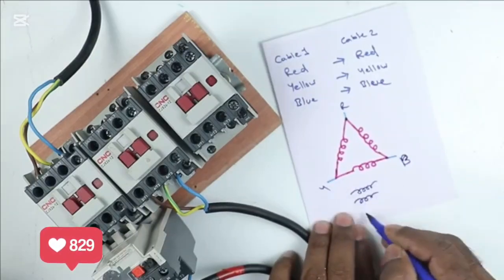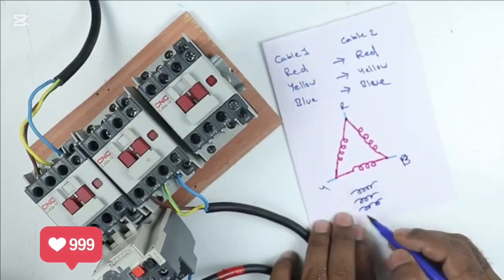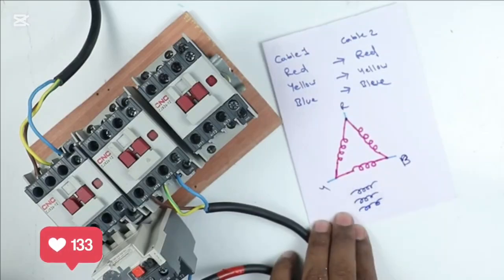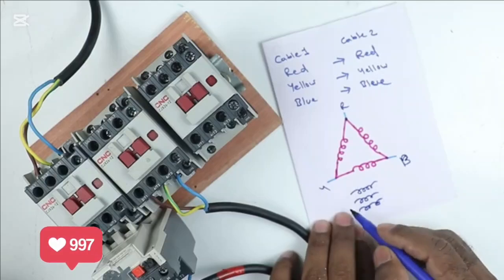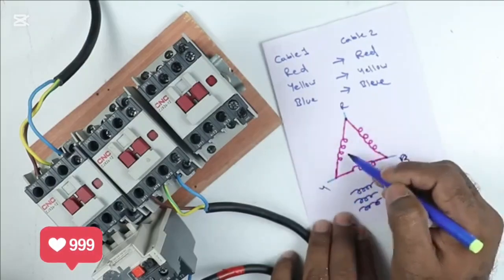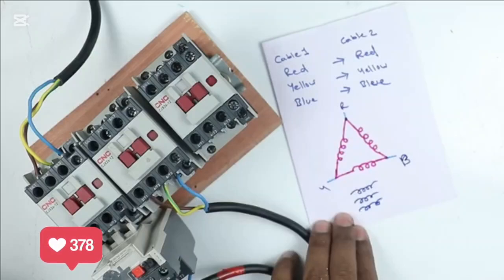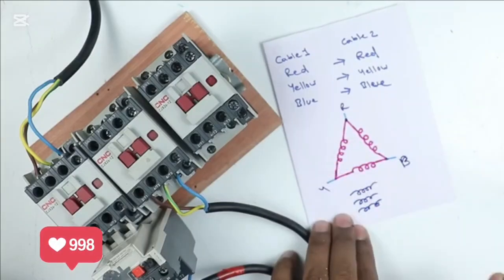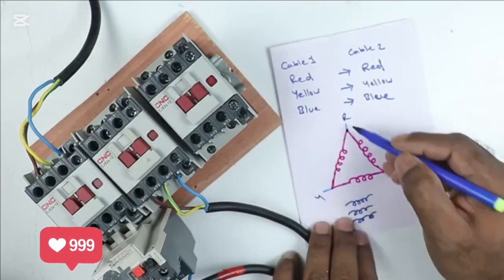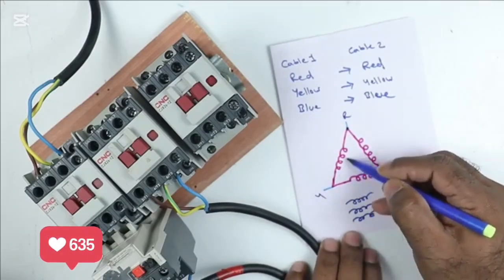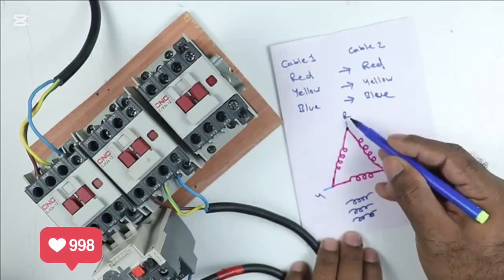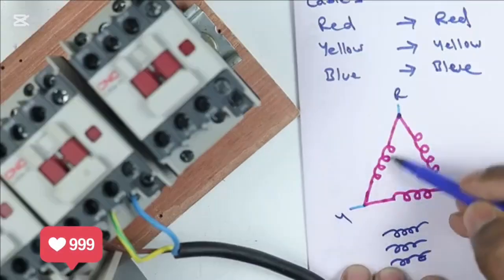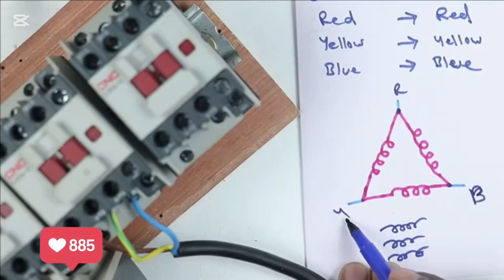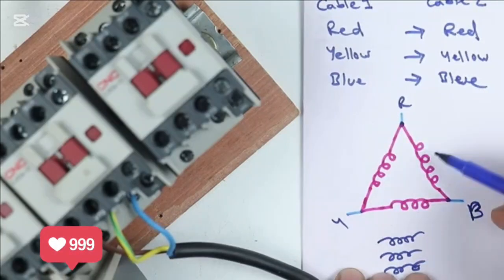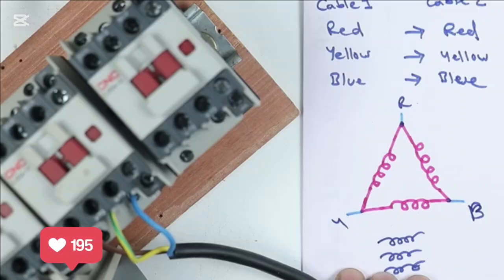Right now the wires which are coming from the motor are in open condition. I mean we have 3 windings and all the 3 windings have 6 different wires. All the 6 wires are different, but we have to connect the wires in this way. For connecting in this way, we are using the contactor. If you want to connect motor winding in this way, then to each winding you have to provide 2 different power supplies. You can see here this one winding. In this winding, here R phase power supply is connected and here Y phase power supply is connected. This winding got 2 power supplies now. In this winding also Y phase and B phase power supply is connected. To this winding, R phase and B phase power supply is connected. Overall the concept here is only to provide 2 power supplies to each winding.